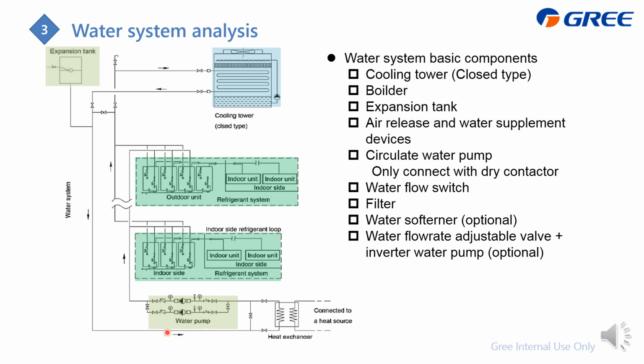For the water pump, it is connected with the dry contactor. We are not allowed to connect the water pump directly. And you need to equip the water flow switch. And this is the boiler for the heating. If the water quality is not that high, you need to apply the water softener to improve the water quality. And if you would like to improve the system operating efficiency, you can adopt the water flow rate adjusted valve plus the inverter water pump to adjust the water flow rate.